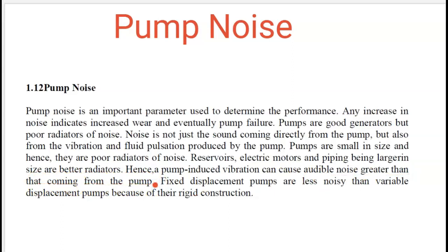So the pump can generate noise, which means there might be a pump down there making the water pulsate, which will result in the whole system making some noise. Like the pump is down there on the ground floor and you are having a noise in the radiator on the second floor. Fixed displacement pumps are less noisy than variable displacement pumps because of the way they are constructed.